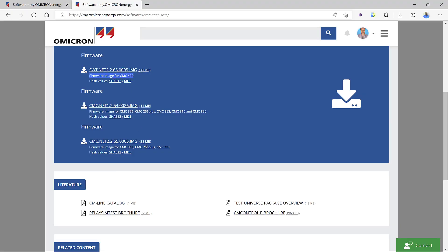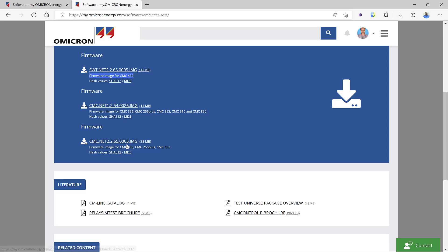Coming back to the Omicron customer portal, my test set has the Net 2 hardware option, so I need the firmware image for CMC 356 Net 2. If your CMC has the Net 1 hardware option — which refers to the communication board on the right side of the CMC — DeviceLink can also help you identify whether you have Net 1 or Net 2. I need to download version 2.65.0005 for Net 2.